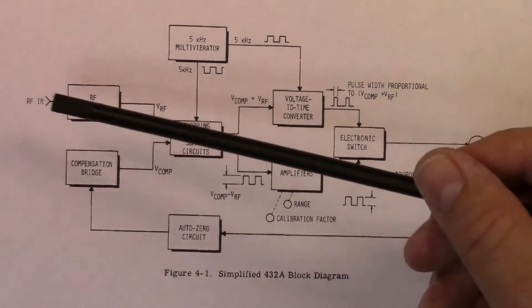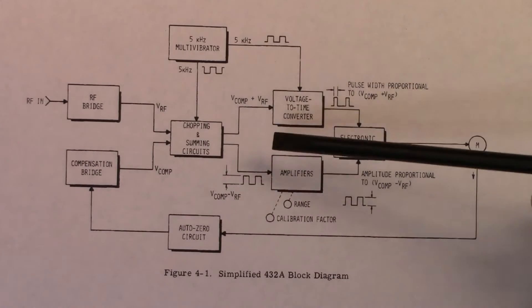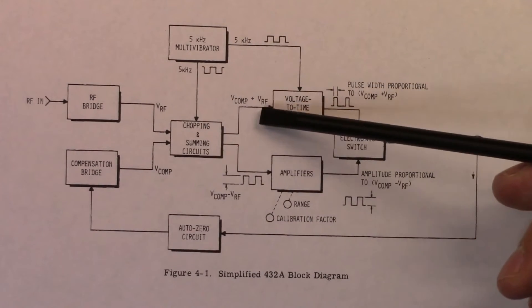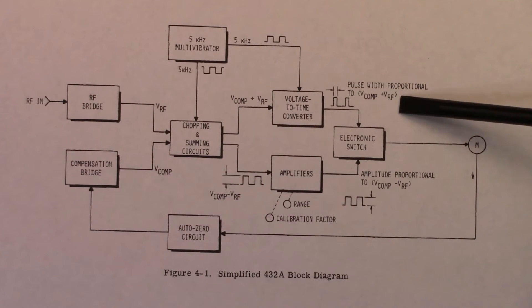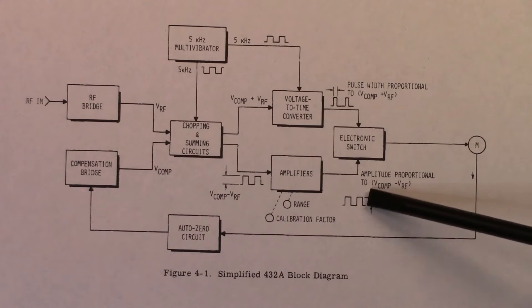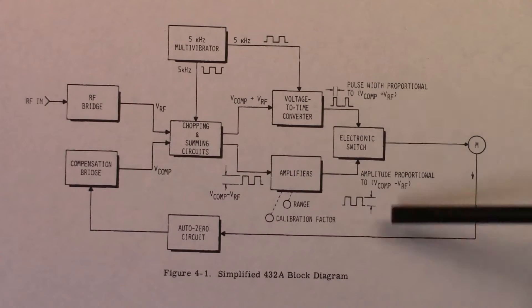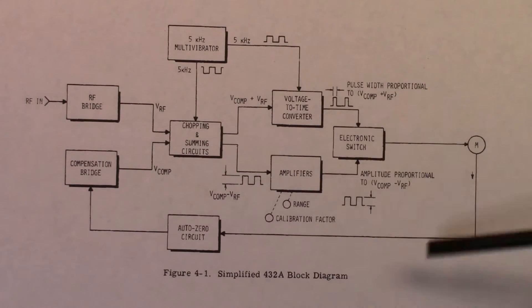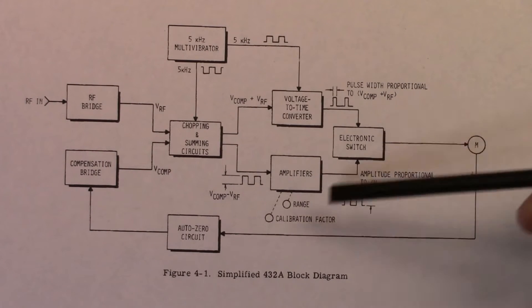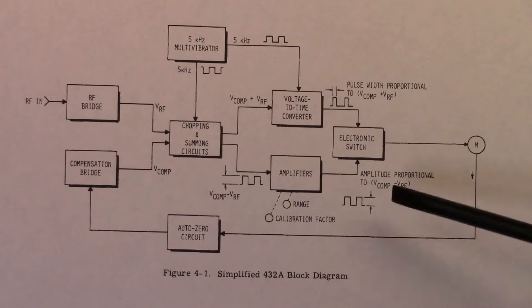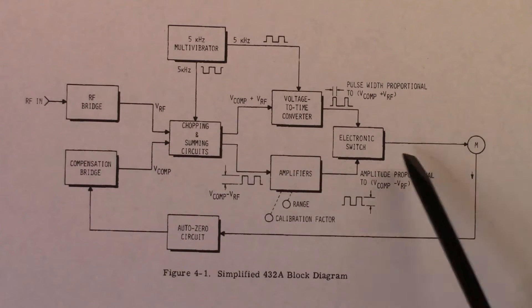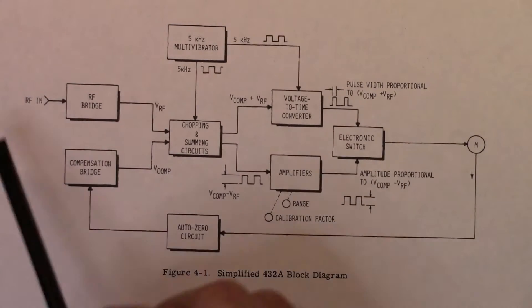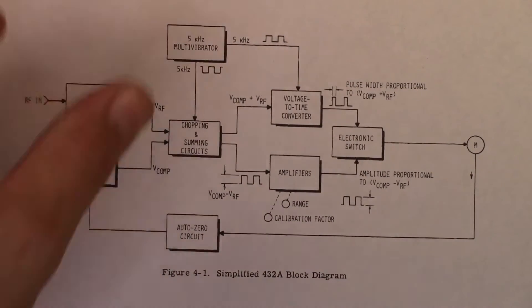Basically what ends up happening is a 5 kilohertz multivibrator creates a Vcomp plus RF and a Vcomp minus RF on this side of the circuit. The pulse width is proportional to the two values. On this side, the amplitude is proportional to Vcomp minus Vrf, and that's how we get rid of the Vcomp aspect. Inside this switch, they're melded back together so the meter sees a set of pulses that have their width and amplitude directly based on the RF signal. We utilize an auto-zero circuit to keep that compensation bridge zeroed.